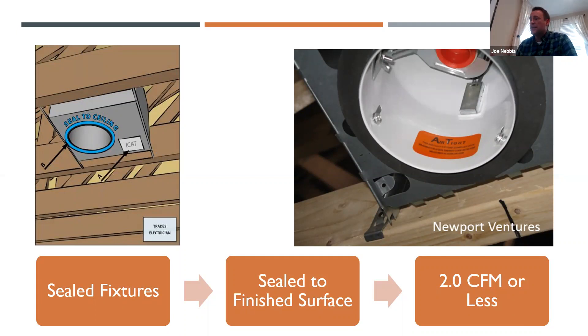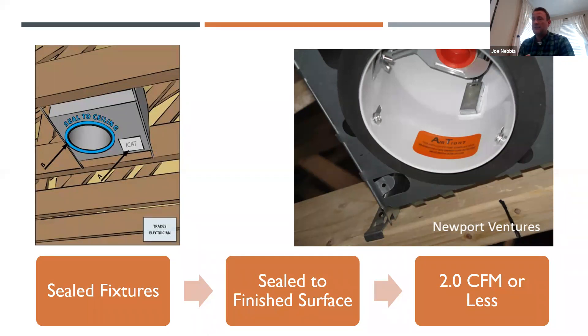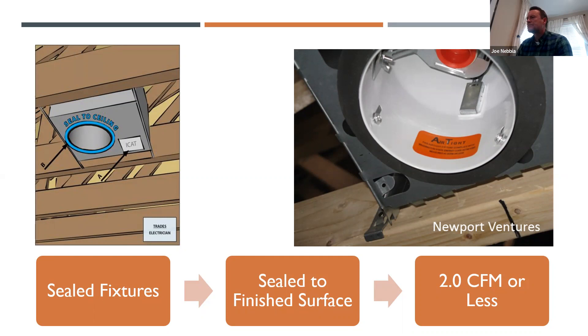Lighting: if recessed lighting penetrates the thermal envelope — top floor going into the attic, that sort of thing — you have to have sealed fixtures. The insulation section also requires they be IC rated (insulation contact rated) if they're going to come into contact with insulation. The fixture itself must be sealed, and then the light has to be sealed to the finished surface. It's not just buying a sealed can or airtight can — that's one step. The next step is that the light itself has to be sealed to the drywall ceiling. That's mandatory.